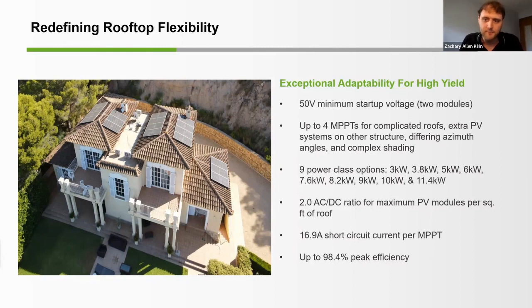The product has a very impressive 200% maximum DC to AC ratio for maximum PV modules per square foot of roof without the need for expensive and time-consuming load center upgrades. A 10 kilowatt inverter can be used with a 20 kilowatt array to oversize the inverter and begin to produce peak energy quickly in the morning. We are proud of our 98% peak efficiency and designed this product to increase the yield for this customer.